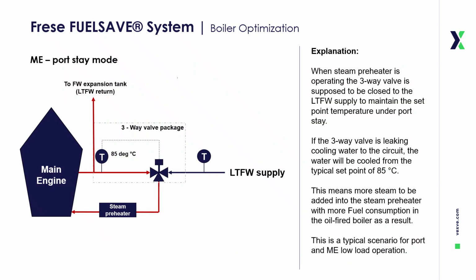This diagram demonstrates the impact of valve leakage on boiler performance. When the steam preheater is operating, the three-way valve should be fully closed toward the low-temperature freshwater supply. If the valve is leaking, however, cooling water continues to enter the loop. This means that instead of remaining at its set point of around 85 degrees Celsius, the water is unnecessarily cooled down. This temperature drop forces the steam preheater to inject more steam to achieve the desired outlet temperature.